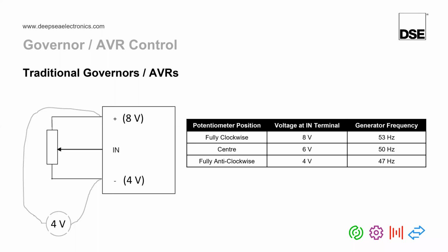So as you can see here, when I apply the center voltage, my generator runs at nominal. And normally this nominal value is actually set by the voltage trim pot or the frequency trim pot located on the governor itself or the AVR itself. Then, as I vary this potentiometer, it goes up 3 hertz or down 3 hertz around this nominal frequency or voltage as set on the governor or AVR itself.